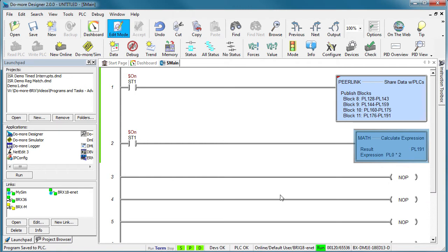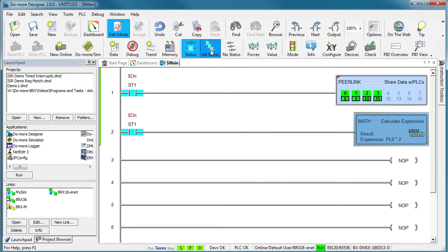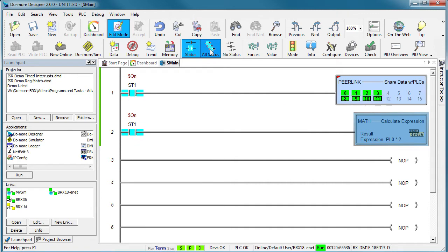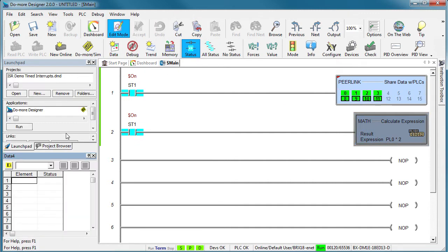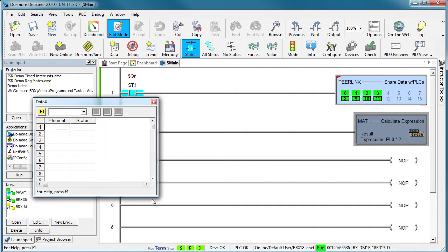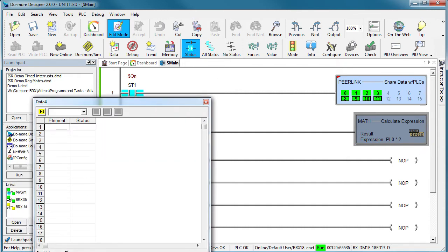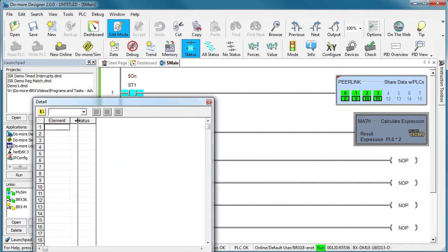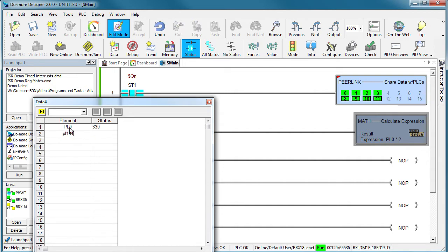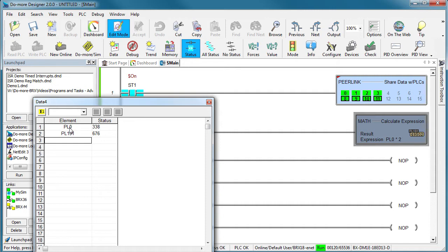If we put this PLC in run mode and enable status, we can see that this PLC is controlling these outlined blocks and someone else is controlling these blocks. Everything is green which means everyone is online and operating normally. If we bring up a data view, we can see what the first PLC is doing to its section of the peer link memory and what this PLC is doing to its section. How cool is that? We can see what the other PLC is doing and we didn't have to do anything except add a peer link instruction to this PLC. Very cool.